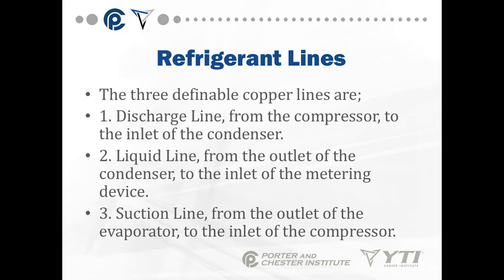There are three definable copper lines in a refrigeration system. First, you have a discharge line that goes from the compressor to the inlet of the condenser. Then you have a liquid line from the outlet of the condenser to the inlet of the metering device. Then you have a suction line from the outlet of the evaporator to the inlet of the compressor.